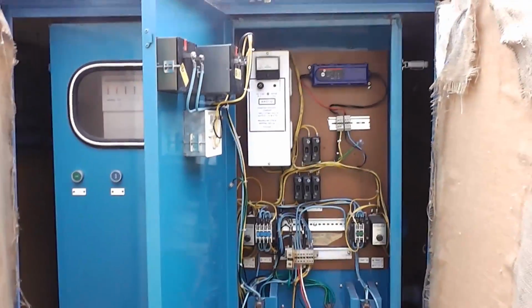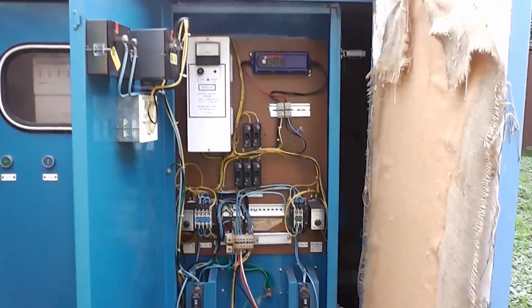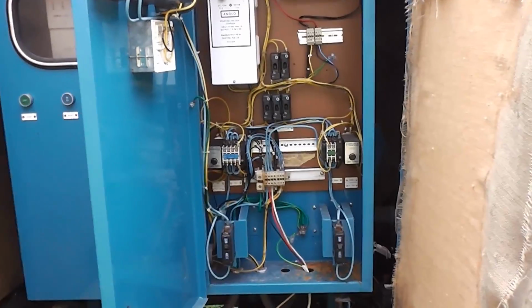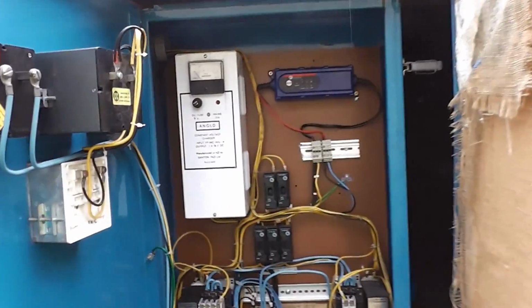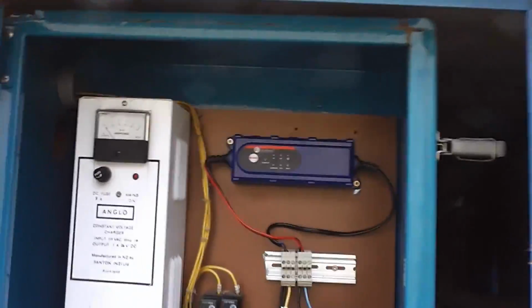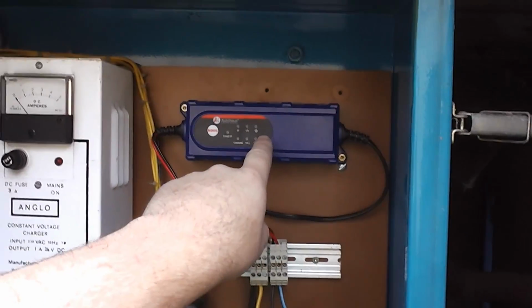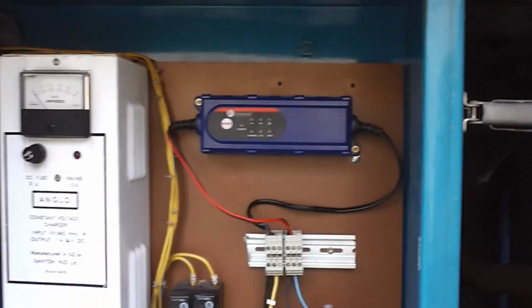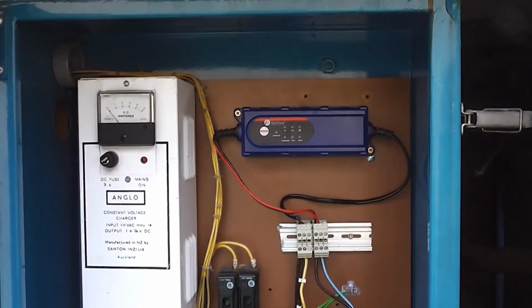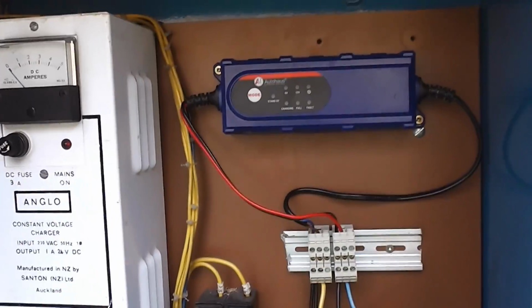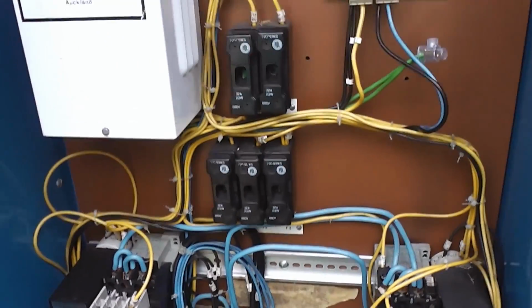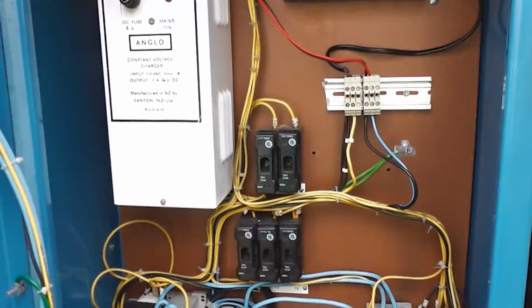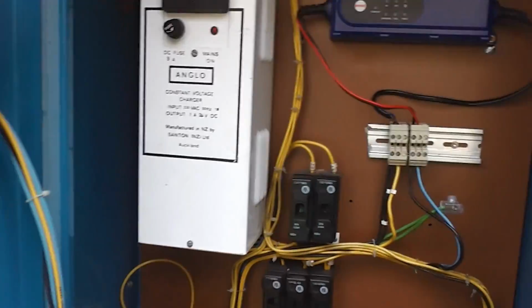Well, this is the panel for the baby generator, and the reason it didn't start is because the trickle charger, this thing that keeps the starter battery topped up, isn't working. It looks like one of these fuses is blown, so I'll have to pull that out and put a new fuse in. First, get a new fuse.